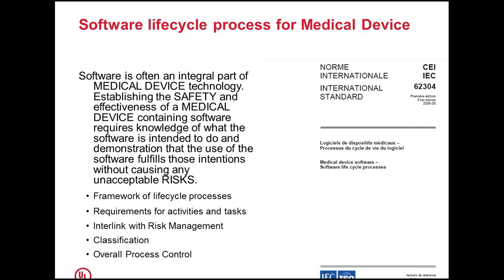Safety and effective functioning of the medical device needs to be looked at from the process point of view — how it has been developed, controlled, released, and how the feedback mechanism works to maintain the software effectively. There is an IEC international standard called IEC 62304, which defines the software life cycle process for medical devices.